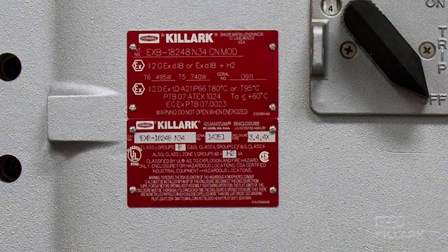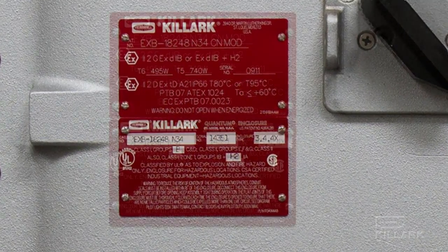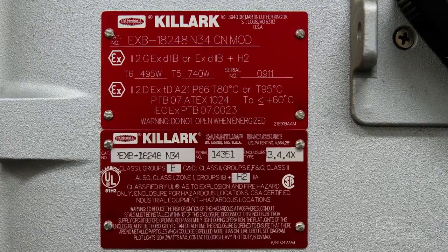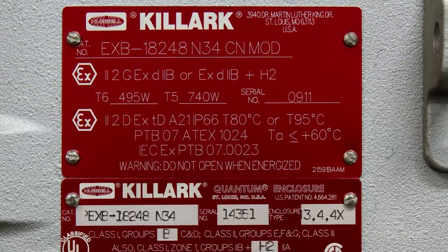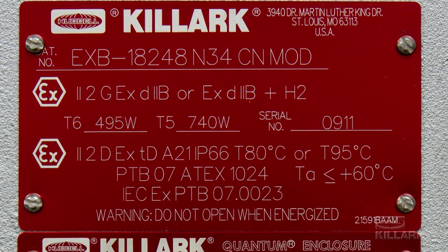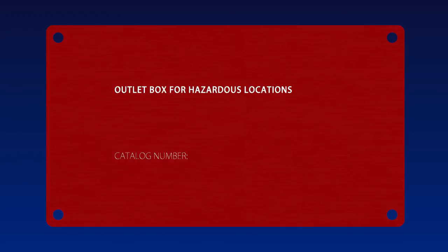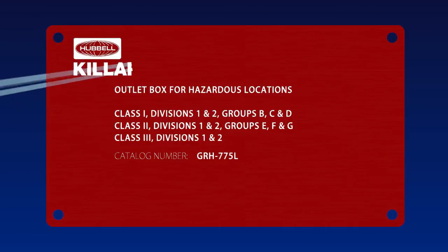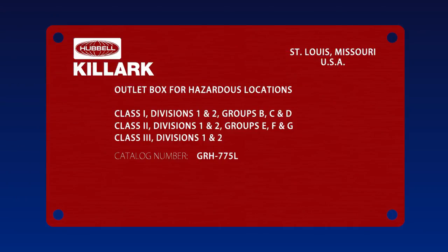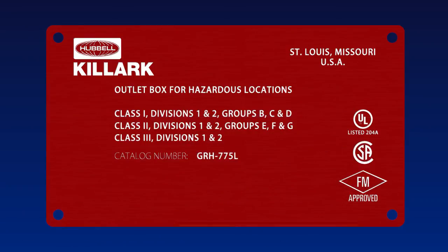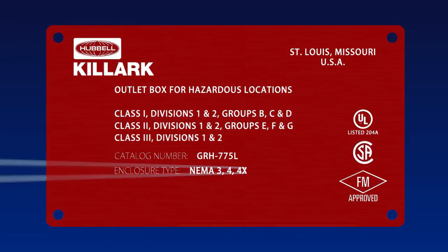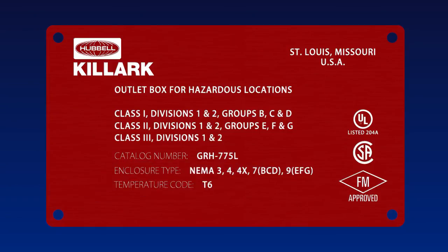Indelible marking of the equipment to be installed is critical for these needs. The codes and symbols that have been assigned to each of the characteristics leading up to equipment selection must be assembled into a surface or nameplate marking consistent with standard IEC practice. As a point of reference, traditional North American marking uses a descriptive approach that includes class, division, and group, along with the manufacturer's name, location, and the certifier's mark. Depending on the product and the application, the NEMA environmental rating, as well as operating test temperatures, could also be required.